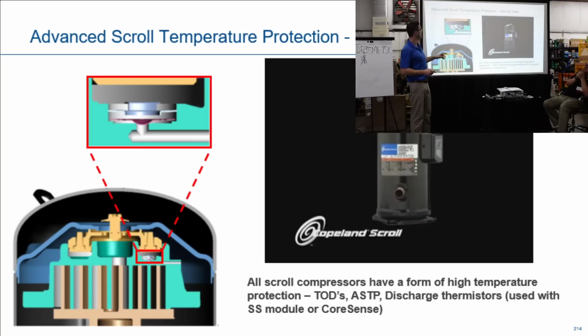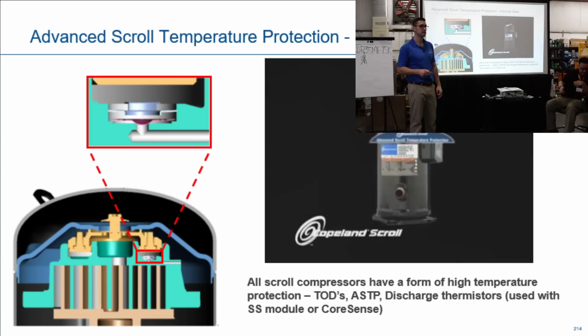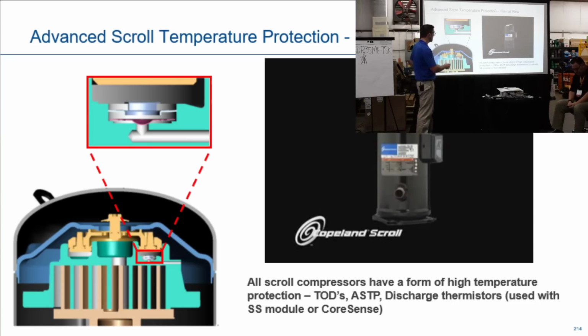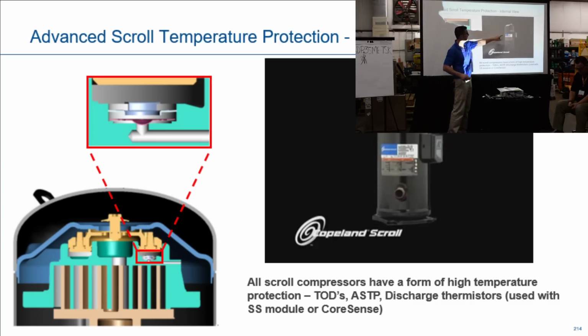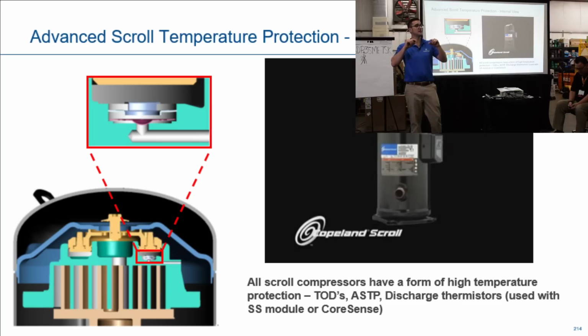So here's a quick video: advanced scroll temperature protection. Anybody hear of this? Basically, it's a device inside the compressor to stop it from pumping. So if your temperature gets over 275, it stops pumping, but the compressor keeps running. So you go up, put the gauges on, and say, oh, it's not pumping, it's a failed compressor. It's not a failed compressor. If you see a sticker on it, like this ASTP sticker that says Advanced Temperature Protection Device, the compressor might not be failed. I've seen multiple ones come back. We put them on our test bench and they run fine. Most likely that temperature was too high, and it opened this bimetal disc and shut the compressor down. Okay?